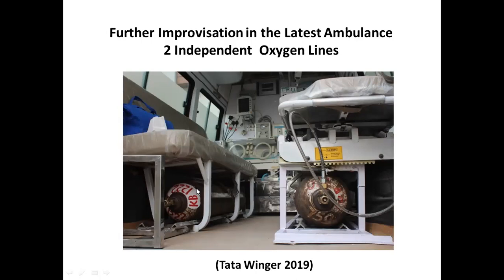See, recently what happened in Goa? Many patients have died. Today the figure is 74. The High Court is asking for an explanation. What has been found was most of the patients had died when the oxygen cylinders were being changed in the main line. Because there's a drop of pressure, ventilators are running, HFNCs are running, there's a drop of pressure, they will not function. And within no time, in a span of 6 hours, nearly 14 patients died. And oxygen was there, but when they were doing a changeover, that took the toll.